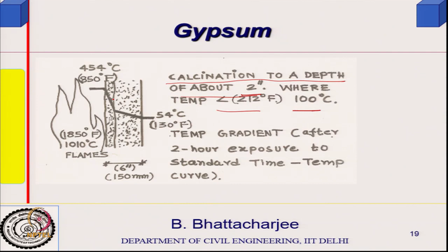When you want to remove the water out of it, this absorbs a lot of heat. So it can take a lot of heat to become anhydrous calcium sulphate. Gypsum will take a lot of heat. So if you have fire on this side, let us say 1010 degrees centigrade in flame, or 1850 Fahrenheit, you will find that a small thickness of gypsum will itself get calcined, to a depth of about 2 inch, or 50 mm, where the temperature will be 100 degrees centigrade or so, because this solid gypsum has absorbed all the heat to liberate the H2O out. So it acts like a heat absorber, a heat sink. That is why gypsum is very good.